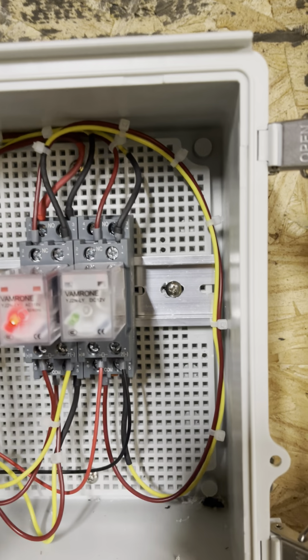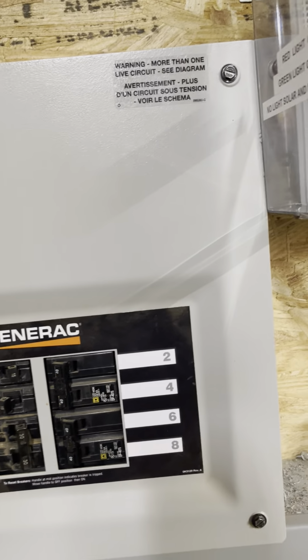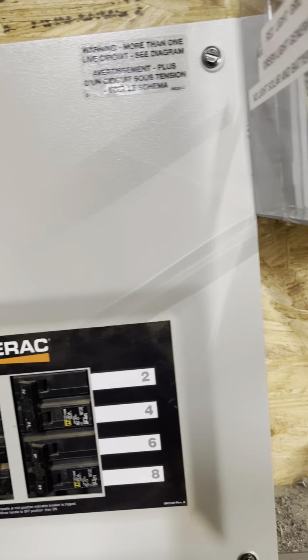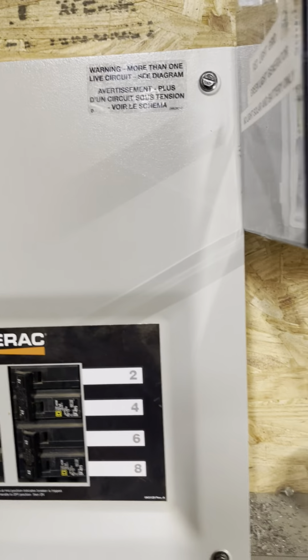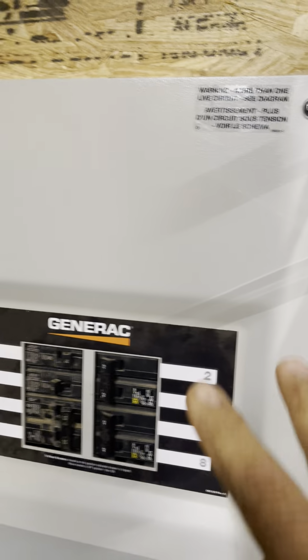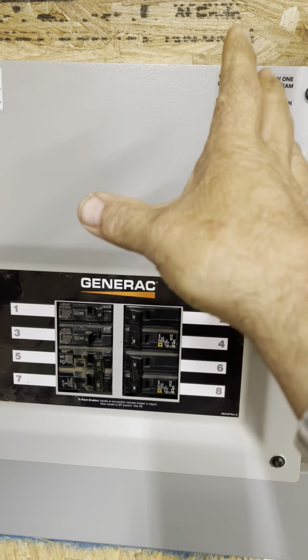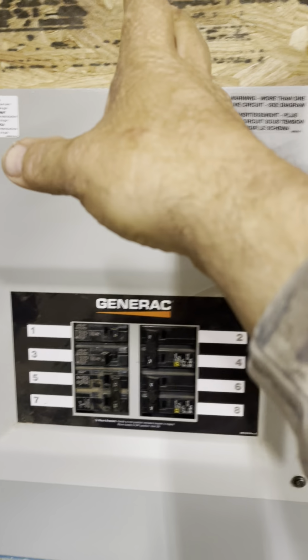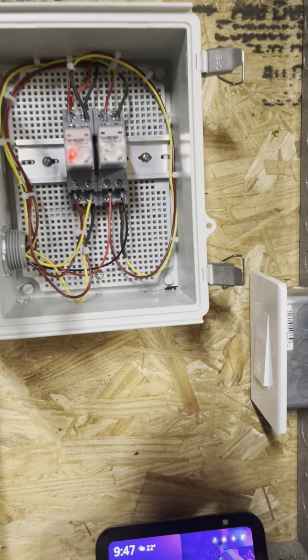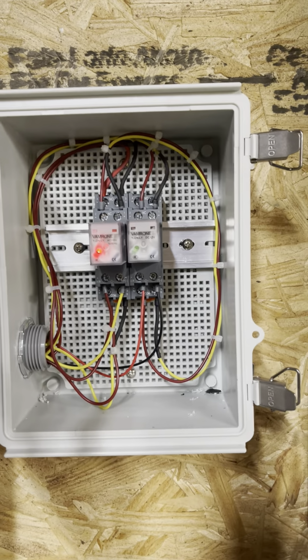Let's start with the high voltage side. It's got a 110 coil, but it's actually got 220 running into it. I took the voltage feeds within the Generac panel that normally go out to the generator, and I came around from them and into here. I came out of here back over to those voltage feeds going to the generator so that it makes a loop. Under normal circumstances, when the power is on, you'll see there's a red LED. That's how the electricity flows. It comes from the main panel through the wire trough into this panel, feeds the voltage sensing wires. The voltage sensing wires come over to this relay, and then back out to the generator. If the grid power fails, this relay will switch over to the other side.